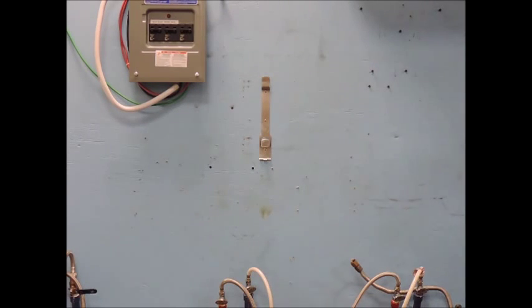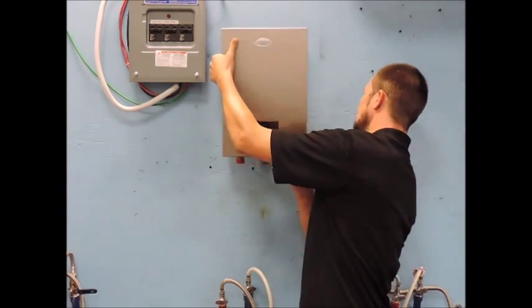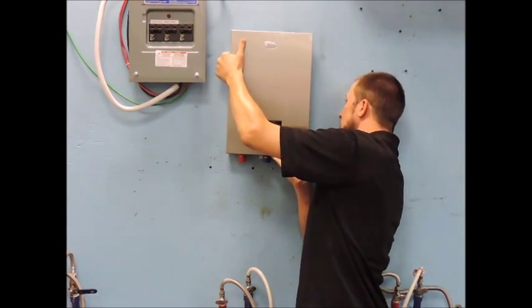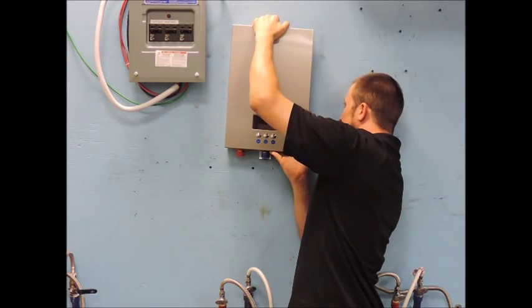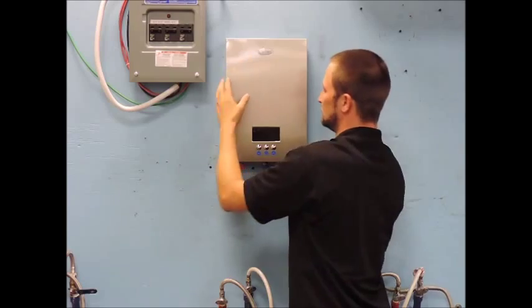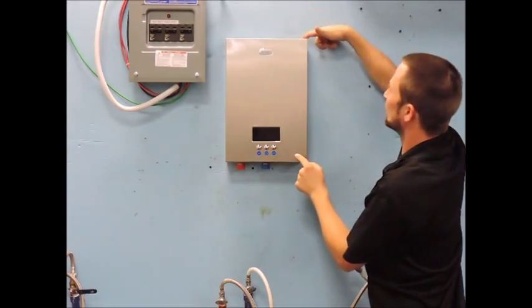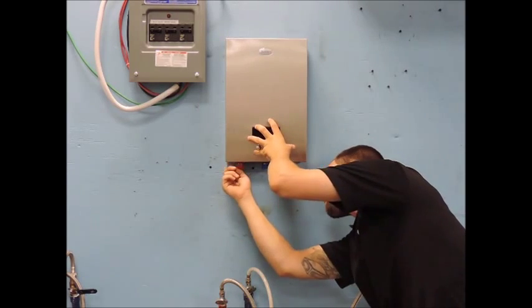Also, confirm that both tabs on the bracket slide properly into the grooves in the back of the unit. Once you have reattached the unit to the mounting bracket, be sure to reinstall the screw on the bottom of the bracket to secure the heater. Please keep this unit away from any potential splashing or leaking water and strong magnetic fields.